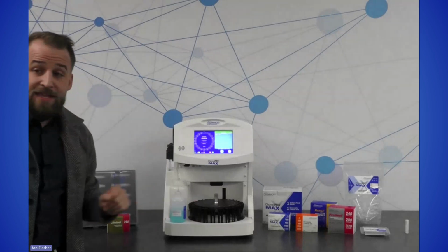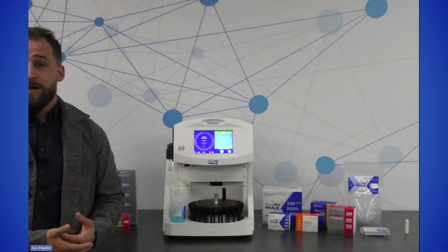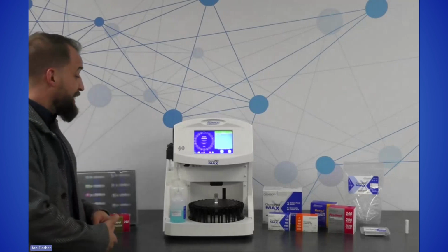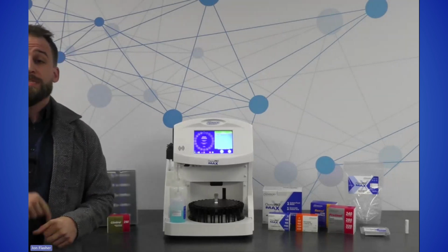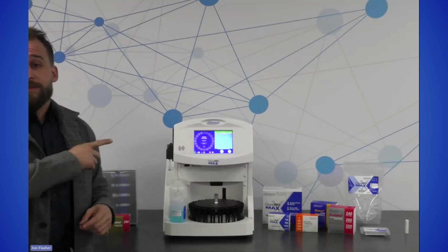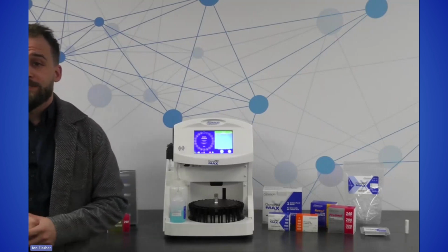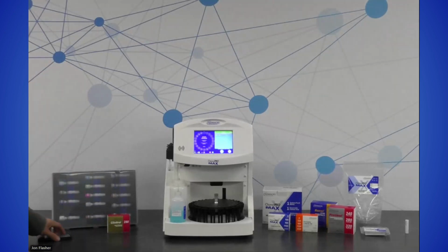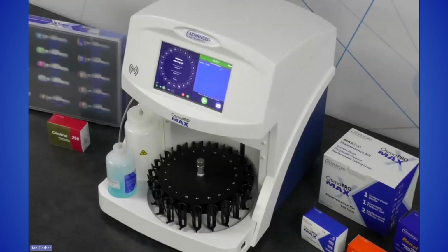And then when you go ahead and load your enzymatic cleaner, which is the final step of the 500 test maintenance procedure, it will not only clean the instrument, but it will use the aspiration of your enzymatic cleaner to calibrate the peristaltic pump and tubing that you just added to the instrument. So dual purpose. Okay, with that said, I think we've covered all of the key software features of the instrument that accommodate continuous and automated testing of osmolality samples, and we covered all of the different consumables that you'll come into contact with in the regular use of the OsmoPRO MAX. So I think all that's left to do now is go ahead and run a sample so we can show you what that looks like.